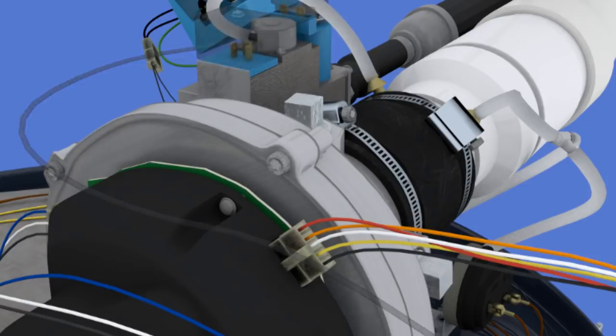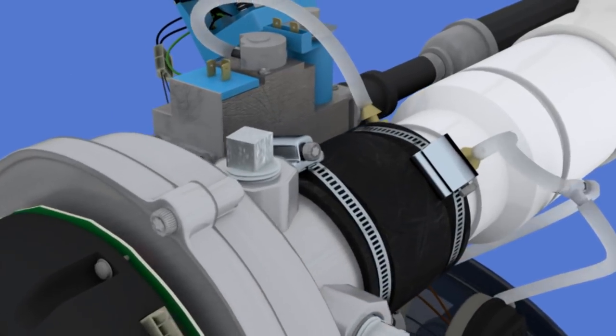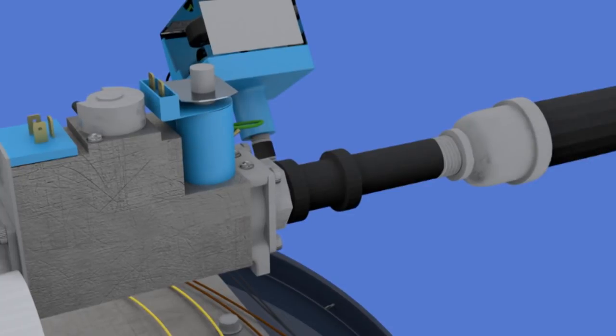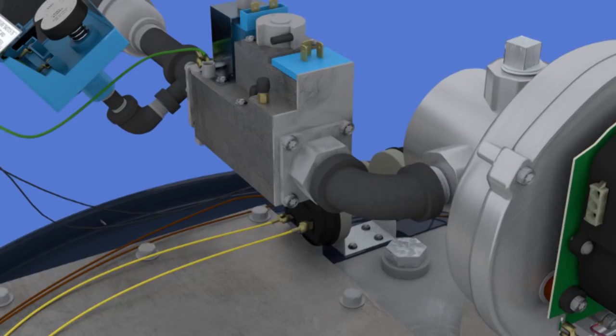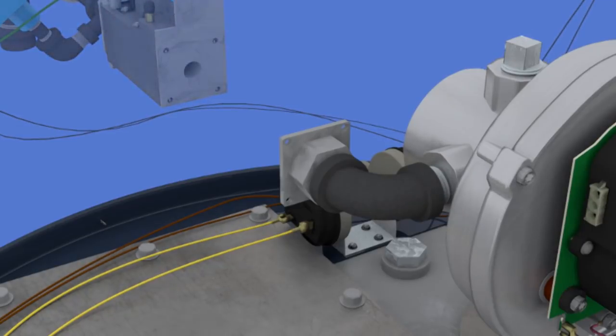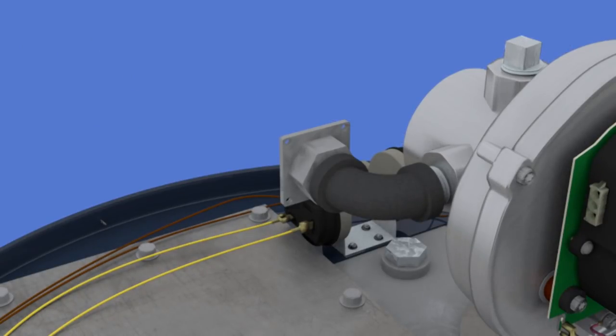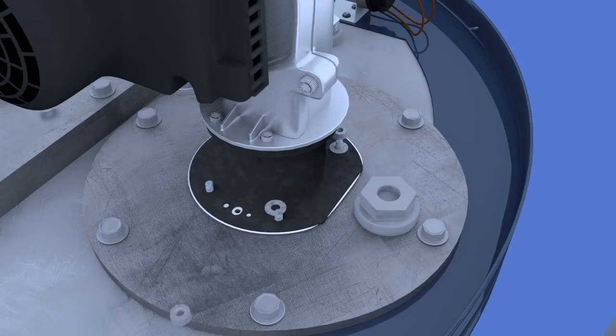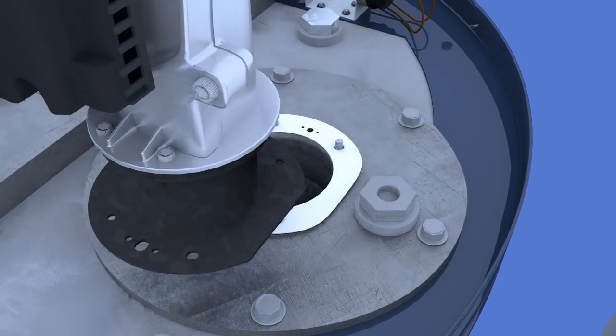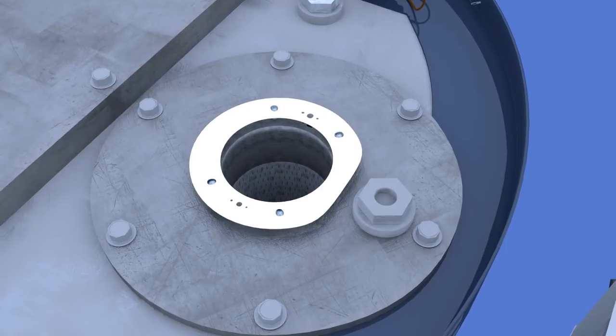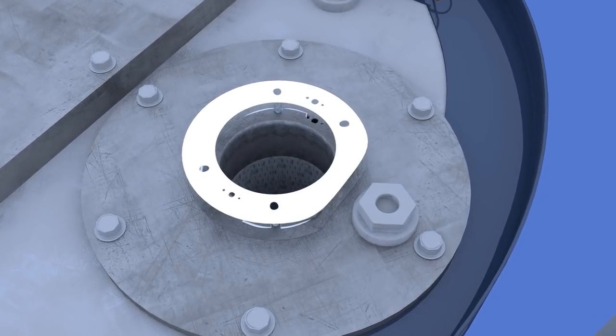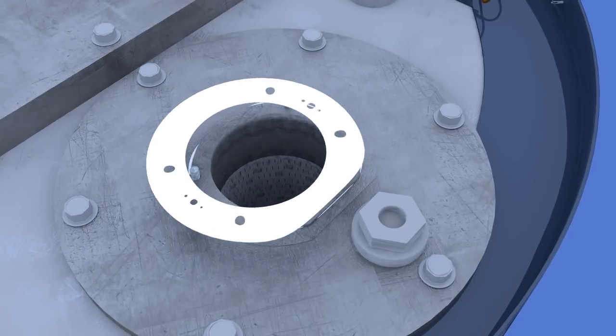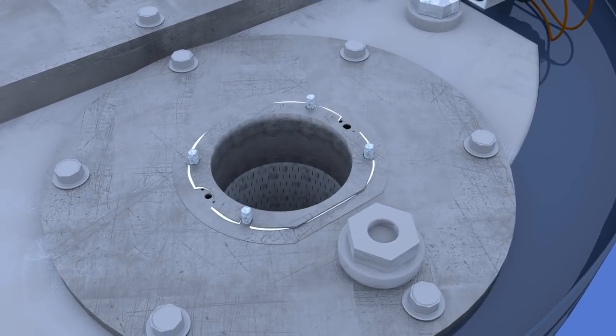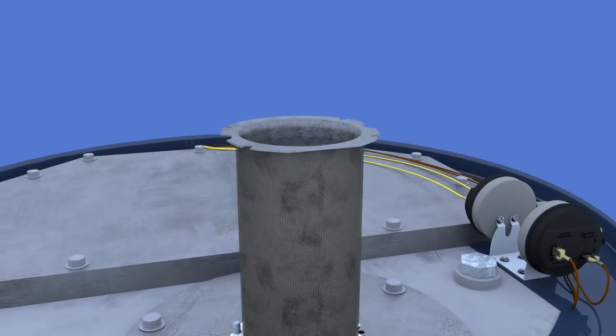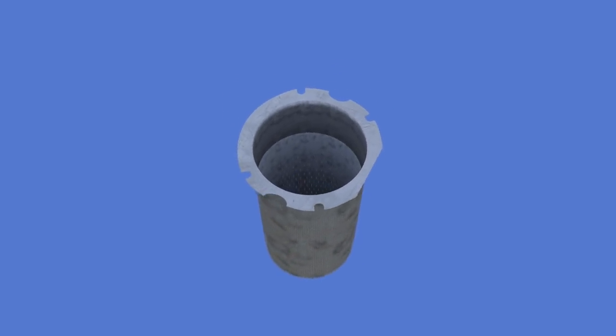Disconnect the wiring harness from the gas valve and the blower. Disconnect the air intake vent piping. Remove 4 screws at the gas control flange assembly. Remove 4 nuts and washers at the burner mounting flange. Remove the blower assembly. Take care when removing all gaskets. Inspect for damage and replace if needed. Lift the burner straight up through the burner assembly mounting flange. Inspect the inside of the burner for blockage.